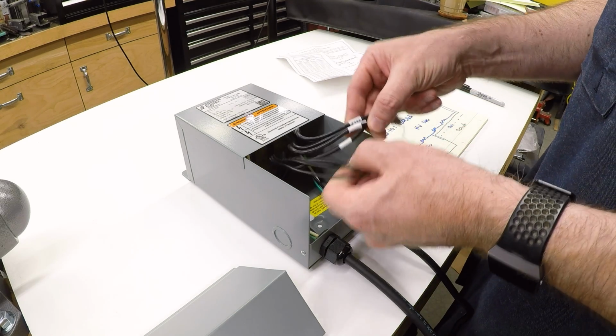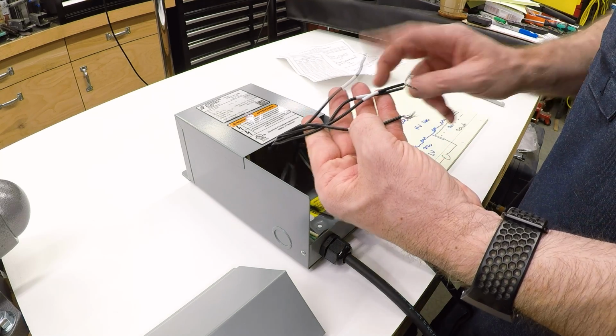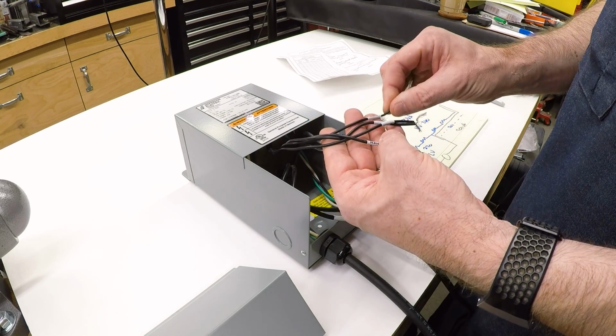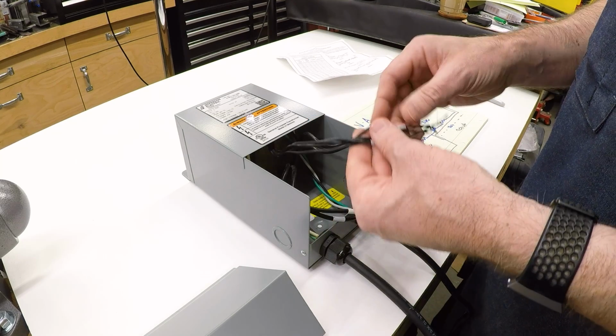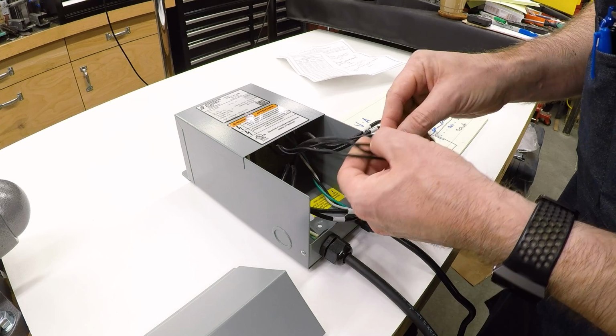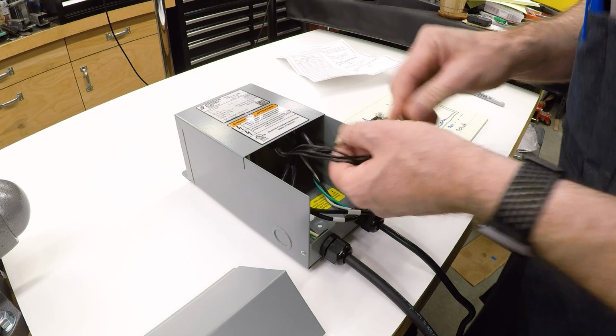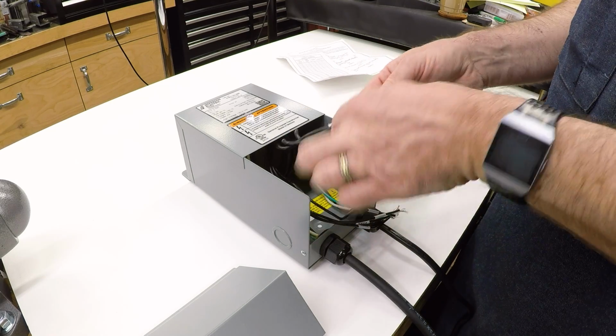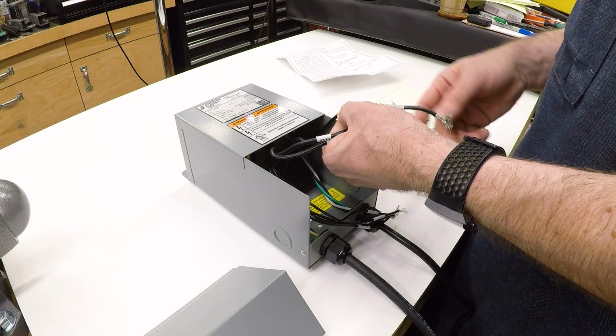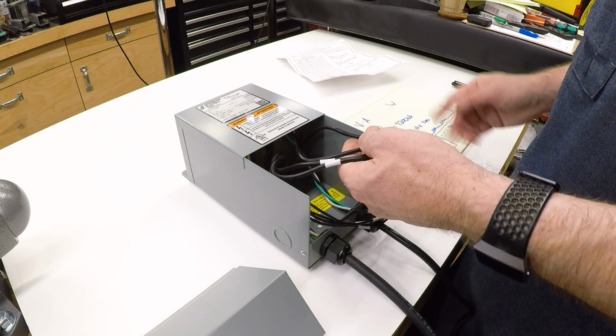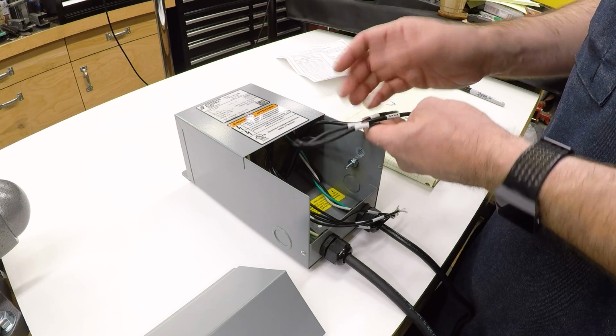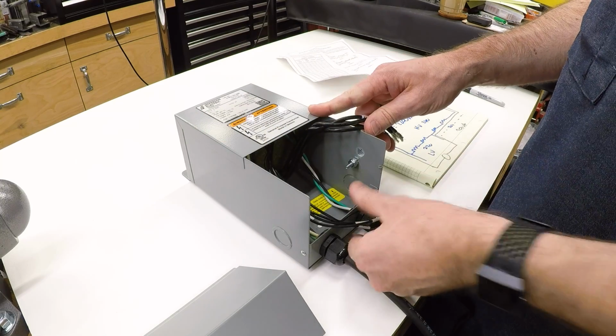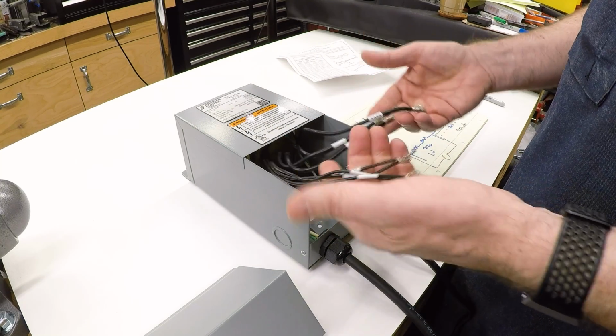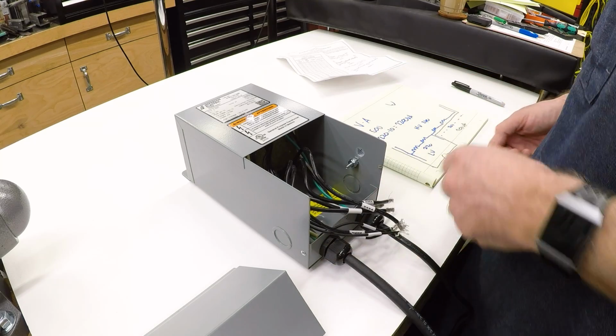If you look at the transformer, the high voltage wires here are small, I think 16 gauge, and the secondary wires are 10 gauge. If you used a traditional primary-secondary transformer, you'd have to have 10 gauge wire and larger coils on both sides of the transformer. So this ends up being a lot more material efficient.